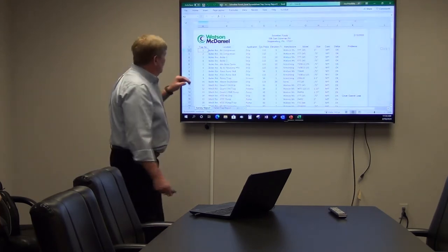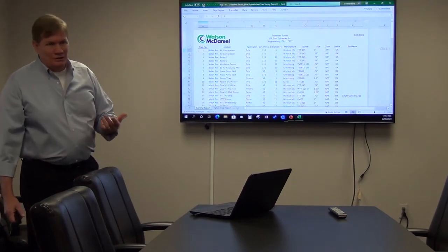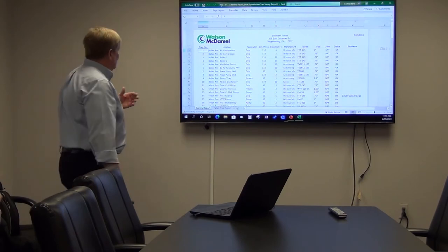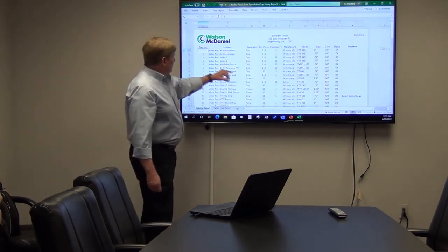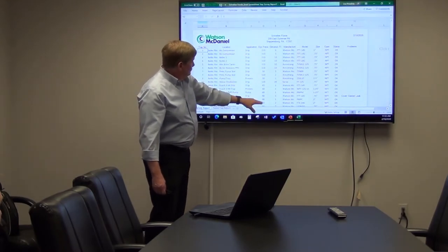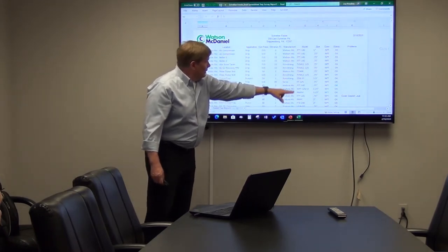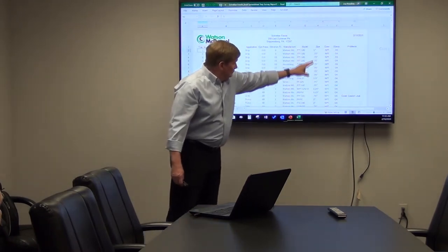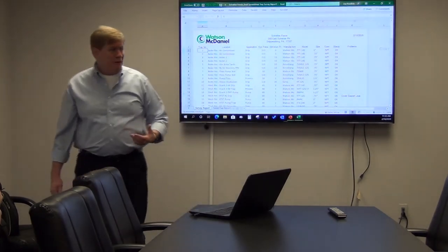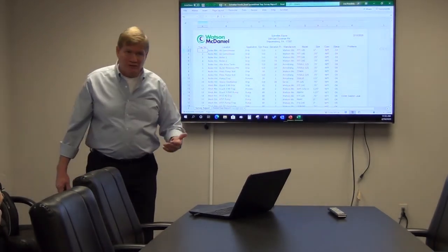So when we do a trap survey report, we partnered a couple years ago with a company called NTRAC, and all they did was trap surveys for the refineries, particularly down in Texas. We'll put all this data in there: the location of the trap, how it's being used, the system pressure, the elevation, manufacturer, the model number, the connection size, whether it's NPT or flange, how it's operating, and other notes that we might see. But now, from your standpoint, you know exactly what Schreiber Foods has at their facility.